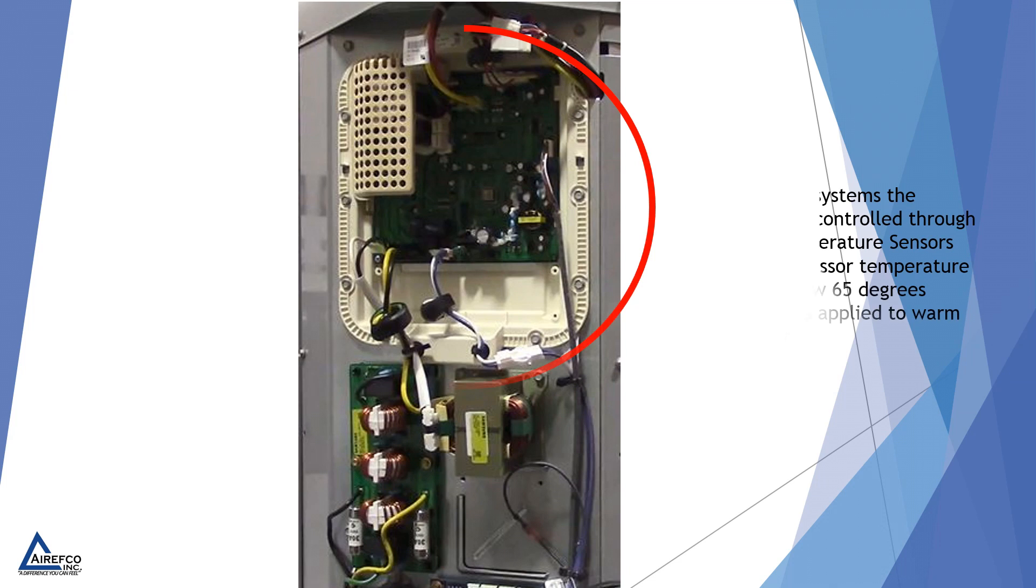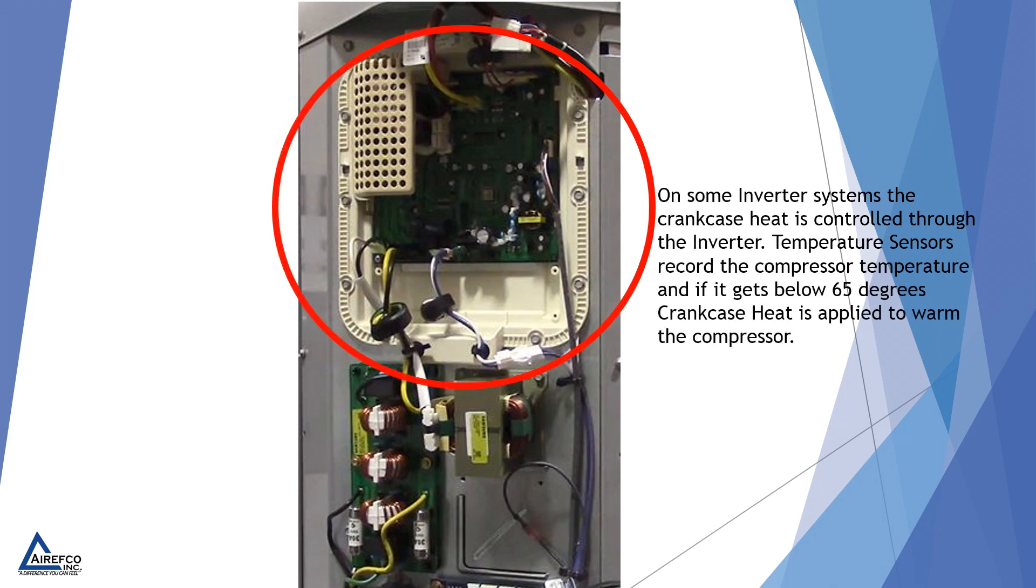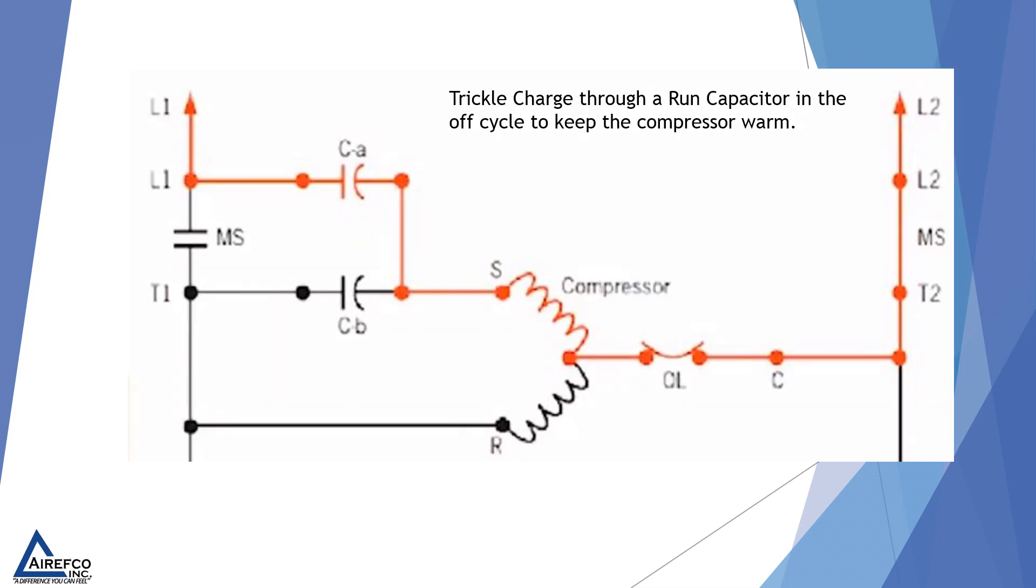On some inverter systems, the crankcase heat is controlled through the inverter. Temperature sensors record the compressor temperature, and if it gets below 65 degrees, crankcase heat is applied to warm the compressor.